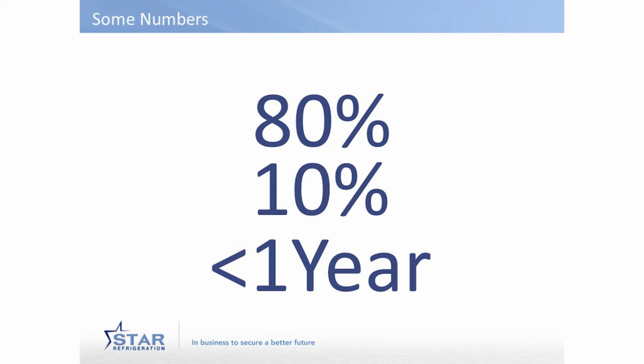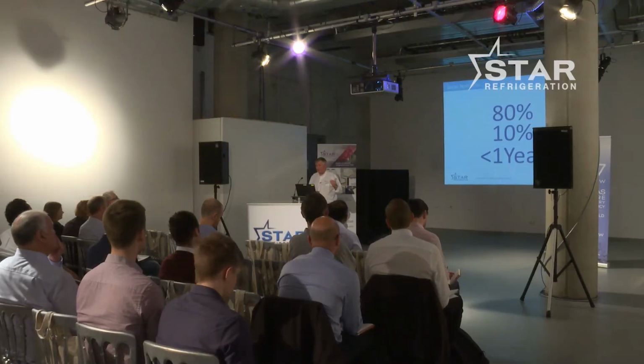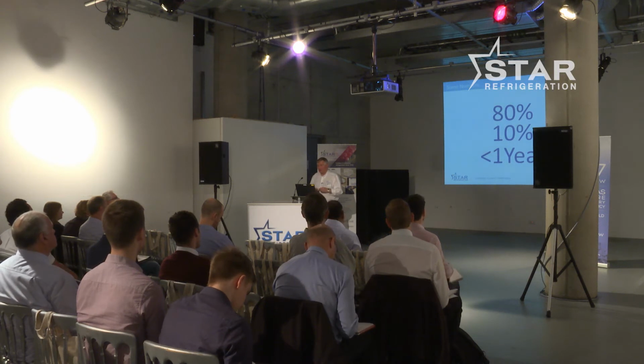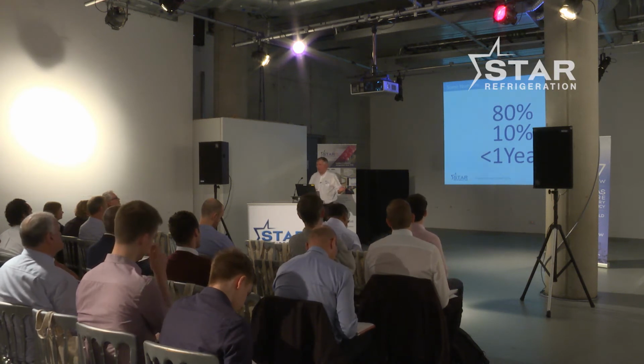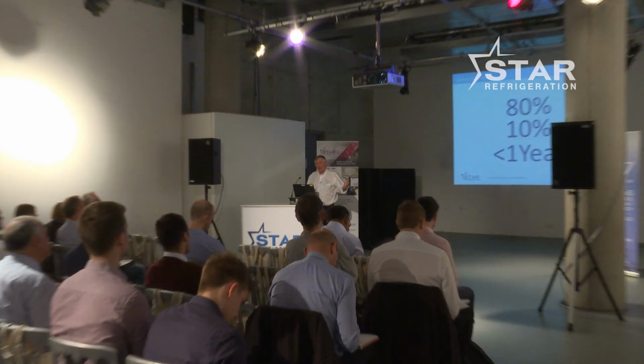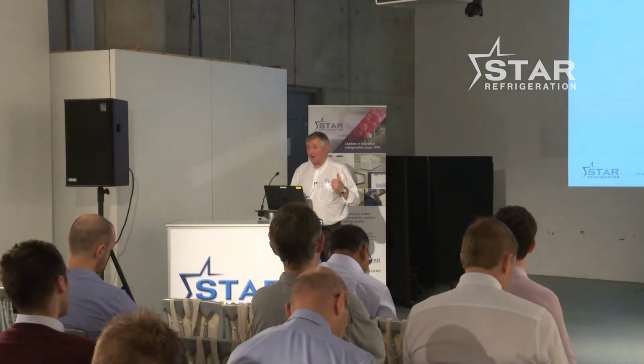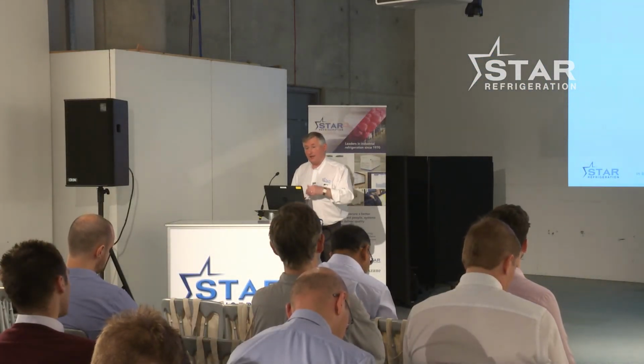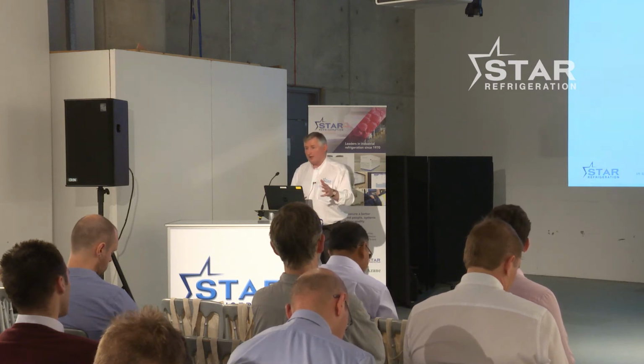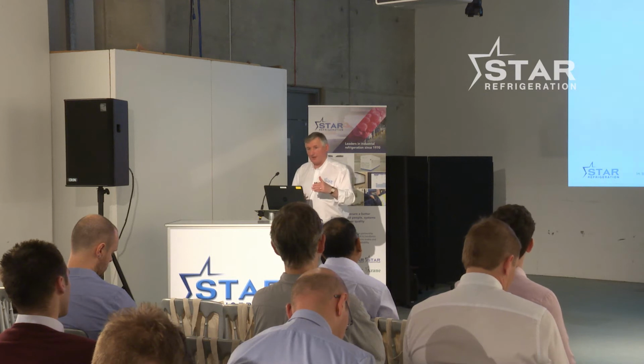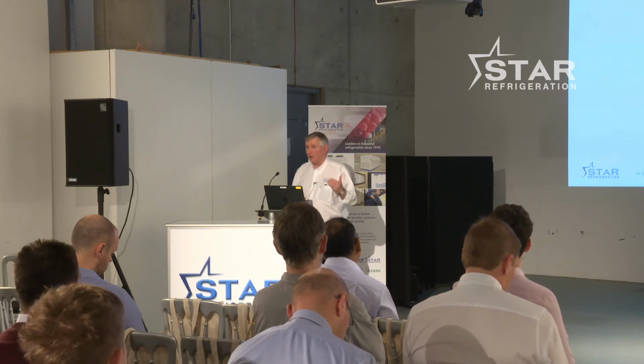It's actually typically the amount that we reckon we could save by going to a typical system that hasn't been particularly well looked after and doing an analysis. It's relatively easy to make a 10% reduction in the energy. And then less than 1 year, maybe a little bit more obvious, if there's that kind of a saving to be made, this is typically the payback that you can be taking to your boss and say, if we do these few small things to the plant, we can save energy and it will have paid itself back within a year. So it really ought to be a no-brainer, but people don't do it.